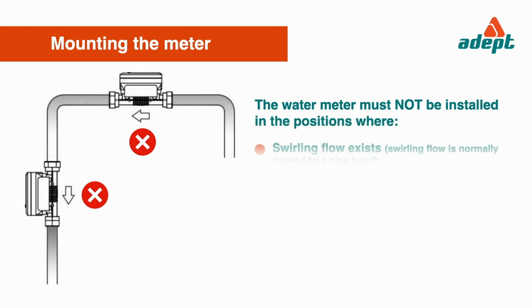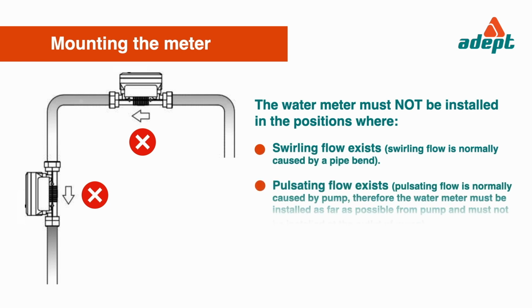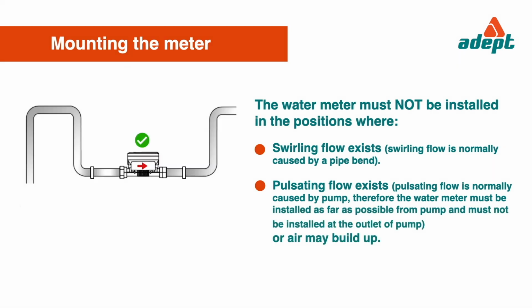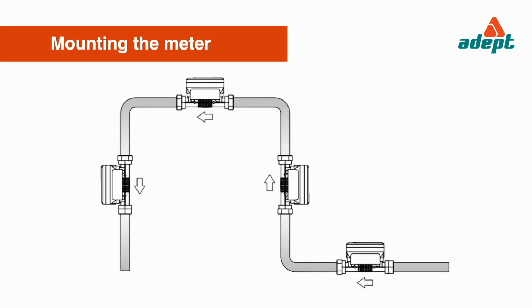Swirling flow is normally caused by a pipe bend. Pulsating flow is normally caused by a pump. Therefore, the water meter must be installed as far as possible from the pump and must not be installed at the outlet of a pump, or air may build up. The following figure illustrates correct and incorrect mounting locations with respect to the direction of flow as shown. Do not install meters vertically where flow is from top to bottom.